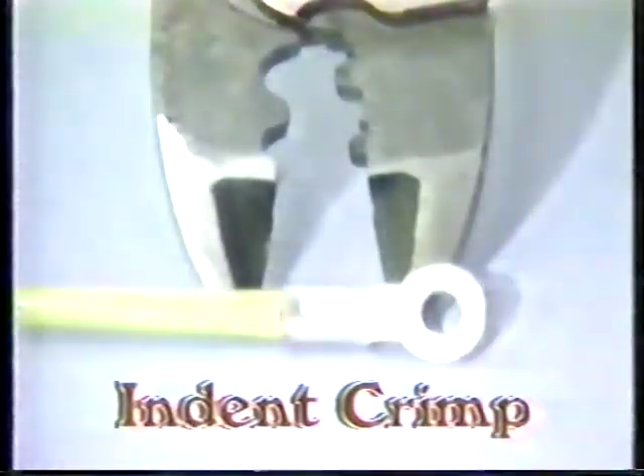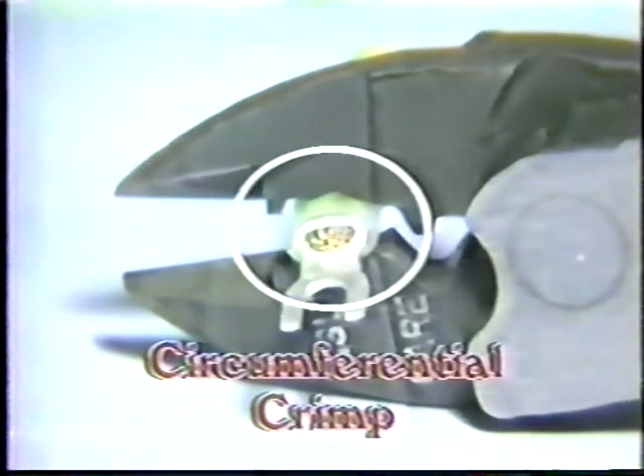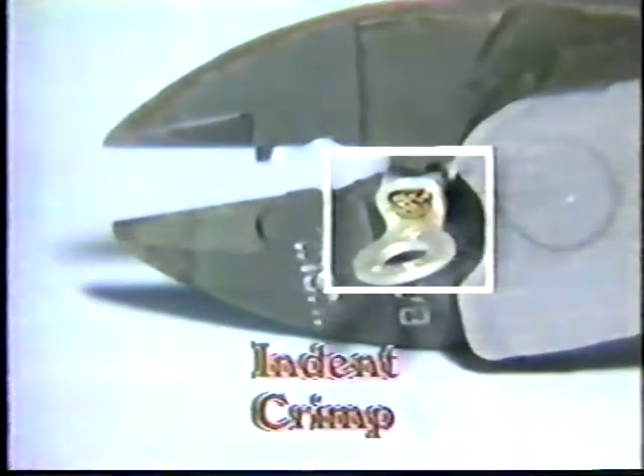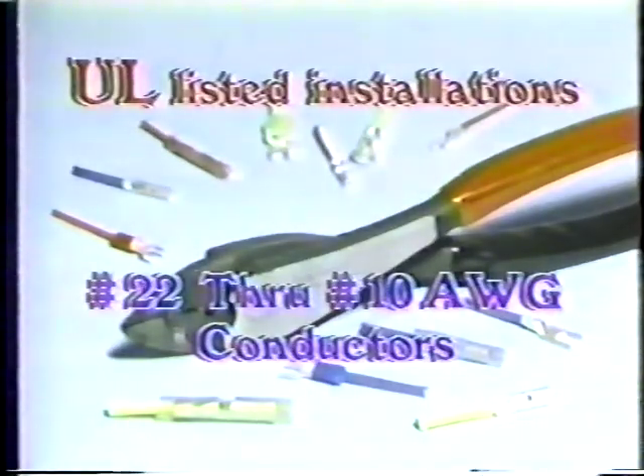An indent crimp is ideal for uninsulated or bare connectors. However, the indent may pierce and destroy the jacket of insulated terminals and splices. Because space may not permit an electrician to carry two crimping tools, Burndy developed the Y10D Hytool, the one installation tool which provides a circumferential crimp for insulated connectors and an indent crimp for bare terminals and splices. The Y10D provides UL-listed installations for the complete range of number 22 through number 10 gauge conductors.